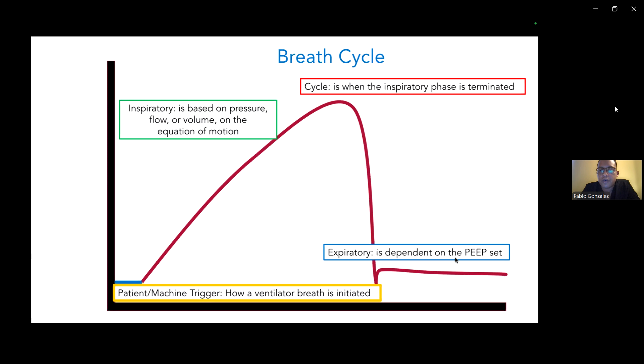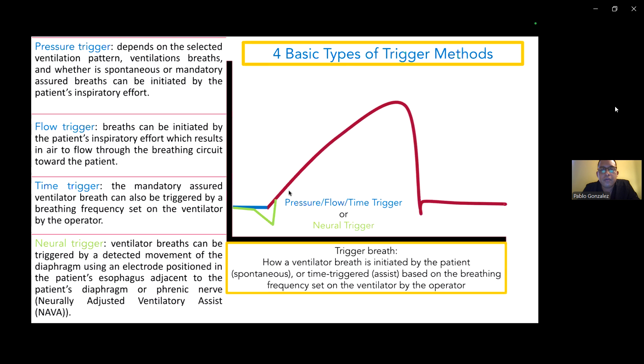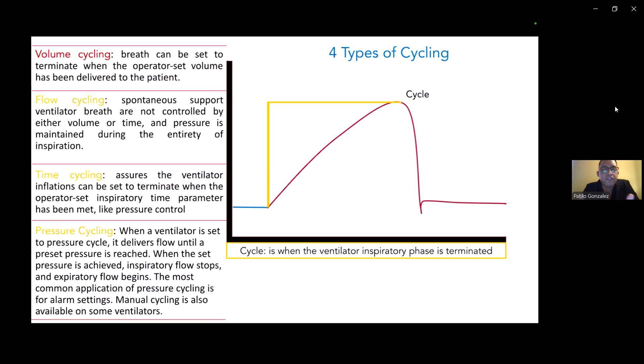There are 4 types of triggers, and the basic ones are pressure trigger, flow trigger, time trigger, or the neuro trigger. One thing to note here: the neuro trigger, I highlighted it in green, but you can see that as the patient pulls, they will pull from your pressure time waveform. There are 4 types of cycling as well: volume cycling, flow cycling, time cycling, and pressure cycling. These are just when a ventilator's inspiratory phase is terminated, in simplicity.